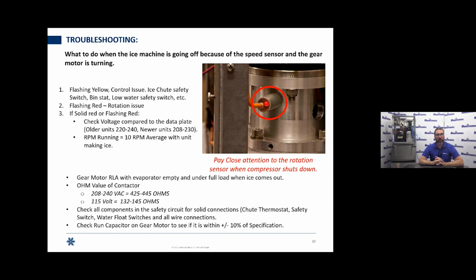If we've determined that we have rotation and we're still getting that flashing red light, we can probably safely assume that there's an issue with the rotation sensor and it needs to be replaced. And again, I talked about if we have a slow flash, what to do there. This is signifying that we have a problem with our motor contactor coil circuit, whether the coil is shorted out within the motor contactor or we just have a short to ground or maybe bad wiring or something going on where we're shorting out.